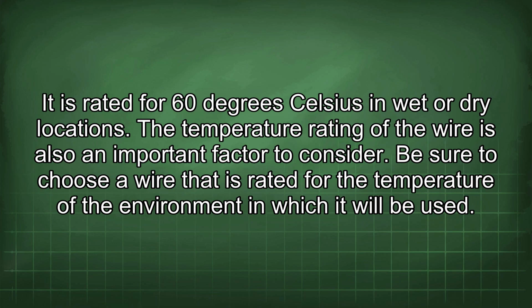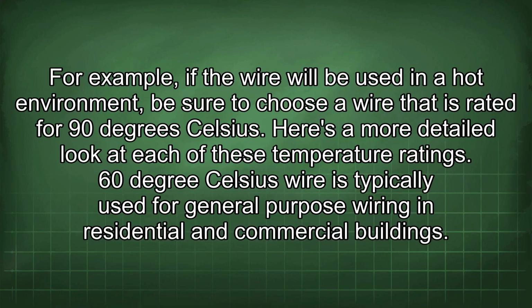The temperature rating of the wire is also an important factor to consider. Be sure to choose a wire that is rated for the temperature of the environment in which it will be used. For example, if the wire will be used in a hot environment, be sure to choose a wire that is rated for 90 degrees Celsius. Here's a more detailed look at each of these temperature ratings.